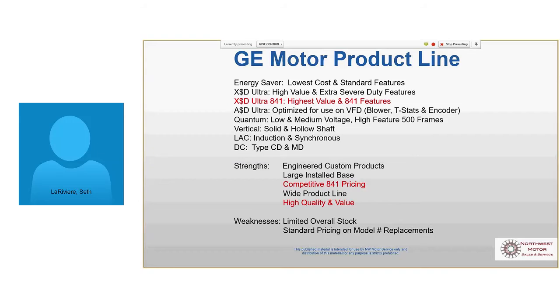Keeps vibration out of the system. So there's a lot of driven equipment advantages to having low motor bearing vibration. They run really cool, so you can put them on VFDs without derating. They're what we stock because it's what all our guys use.